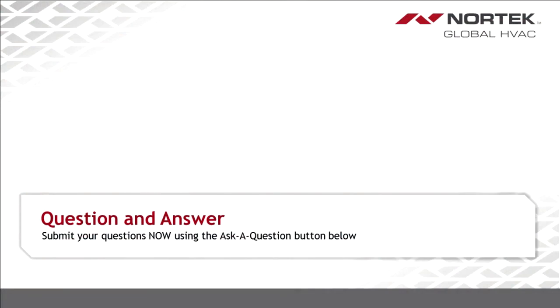So, very good question, and very important to remember that whenever you're setting up the speeds on the indoor unit, you're setting it for 100% of the blower capacity. So we want to make sure that we're utilizing the Y/Y2 on the indoor unit and the Y outside for single stage, and that'll give you 100% of whatever you set that blower up for. If you use Y1 and Y outside, then you're going to have the blower running at a lower speed, and you're going to end up not having enough airflow for heating and cooling mode. So that was a great question. Whenever you're ready, Dana, feed me another one.